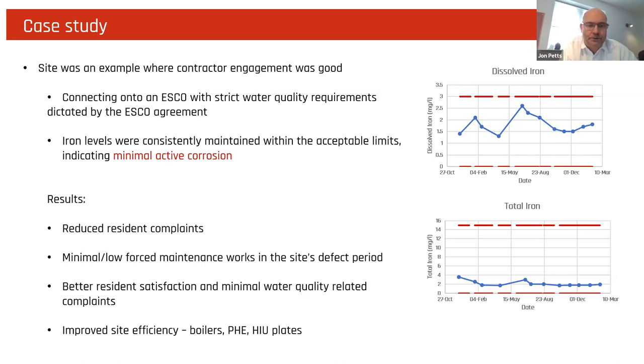That particular project was connected to an E.ON ESCO supply with an external district heating network. ESCOs are particularly hot on water treatment. So although you may have a plate heat exchanger, the downstream side of which is within your control, you may have elements of primary pipework where you're connecting to valves, etc., from the ESCO before it's got the hydraulic separation. And the ESCOs will be all over you, making sure that you've got the correct flushing procedures and water treatment in place, cleaning their section of the pipework before it's all opened up to their system. Because obviously they don't want to risk contaminating a whole wider network, which could cause damage to multiple properties.